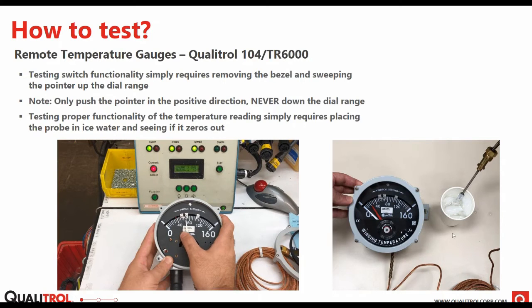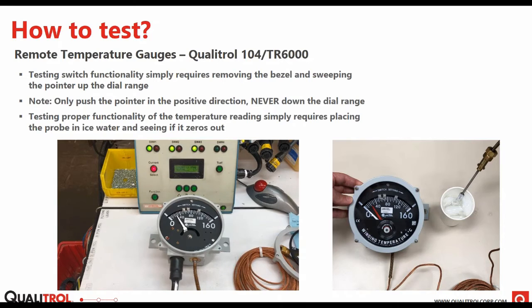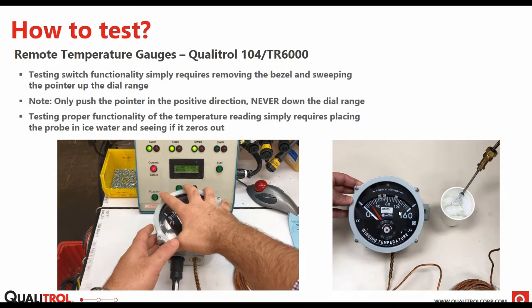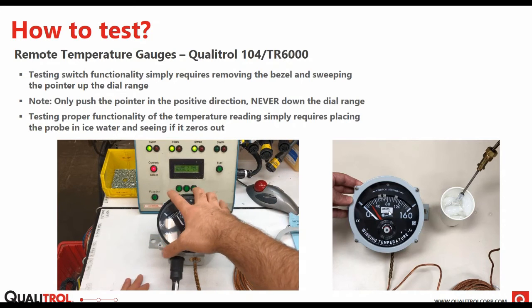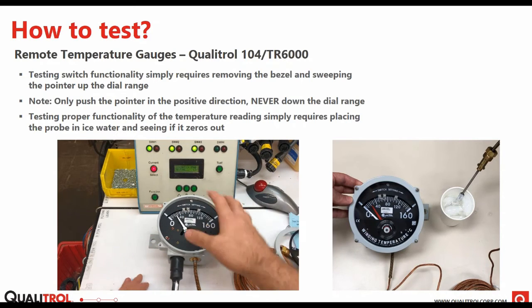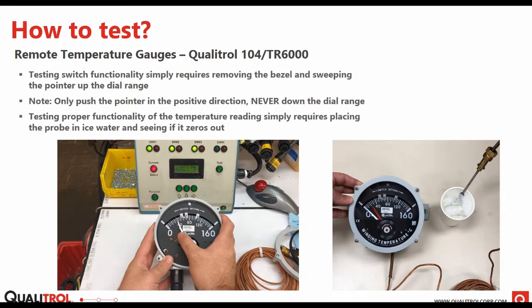Another quick and easy field test, which you can see on the right here, to test actual functionality of the thermometer itself, is just an ice bath test. What this does is, once you put it in the ice bath, it's going to zero out. You want it to zero out. And if it doesn't, that can lead to other issues, like say there's a leak in the capillary, because this is a high pressure capillary system. There could be a leak. The preload, there could be an issue with that on the gauge. So you really want that to zero out, and that's a good quick way to do a functionality test.